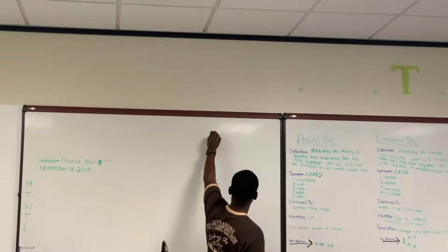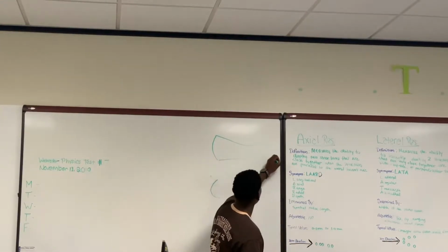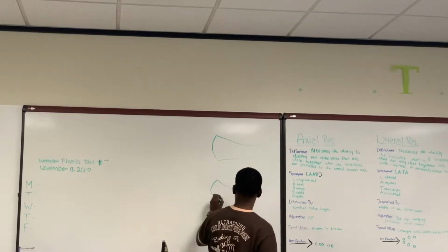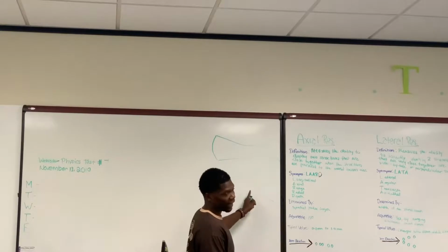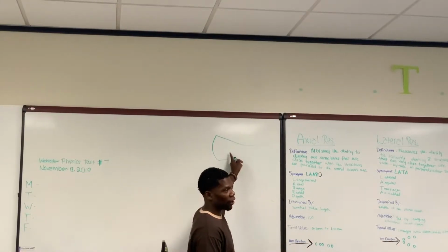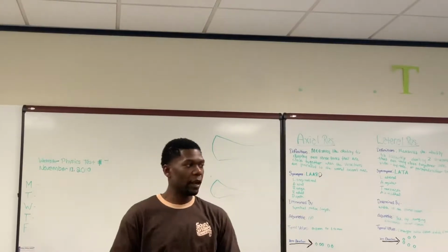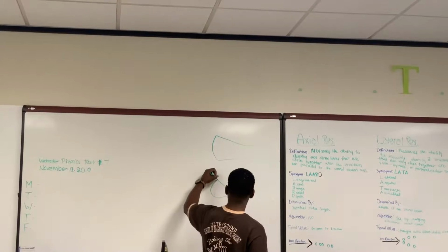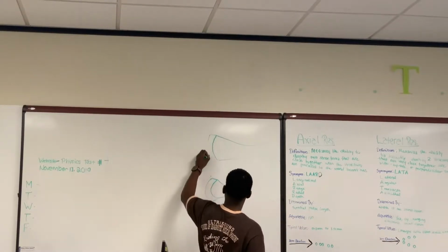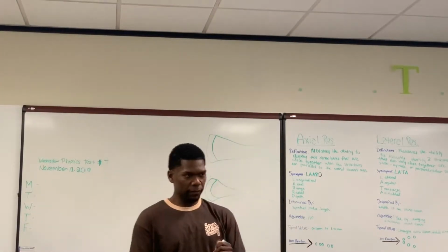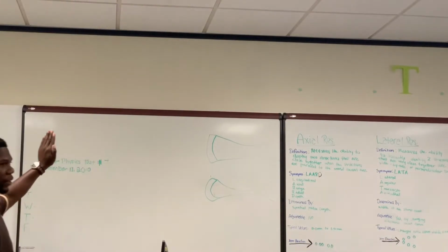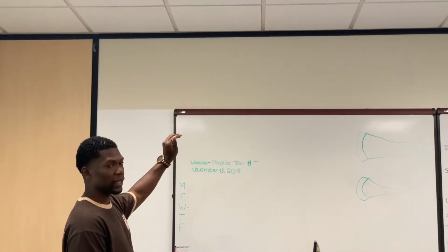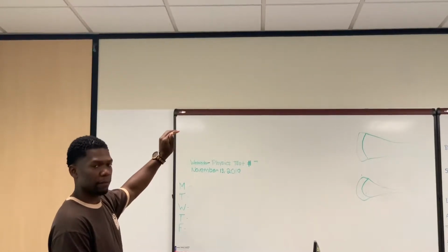So I'm going to exaggerate my point right here, guys. But this arc is more prominent, it has a steeper arc to it, right? So my focus is going to be able to be focused a lot more. My focus is going to be a lot thinner. The beam is going to be a lot thinner at the focus because of the arc of the acoustic lens. Okay? That also applies to the PZT as well, the curved PZT. The degree of the arc, how much it is arced. And y'all understand what I mean? As far as like, if I have an arc like this, that's not going to be a really thin focus. The beam is not going to be that thin at the focus. But if I arch it like this, then I'm going to have a really thin focus, a really thin beam at the focus. Okay, that's what I'm trying to say.